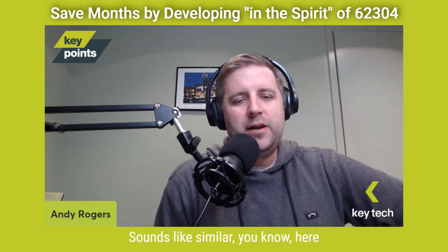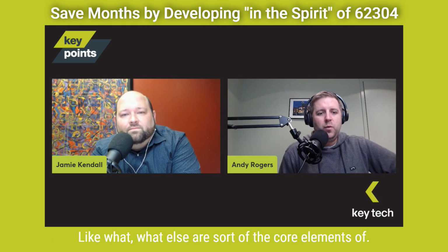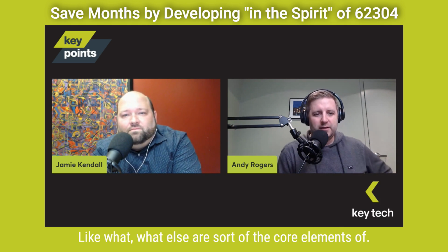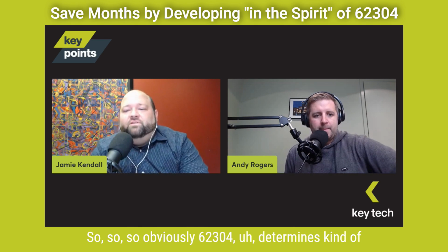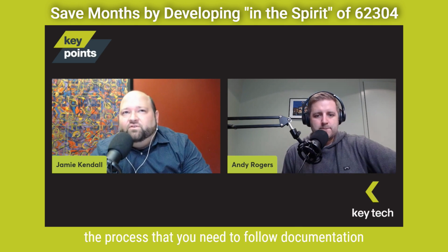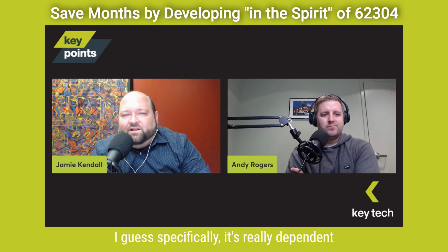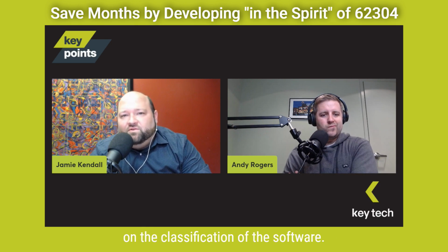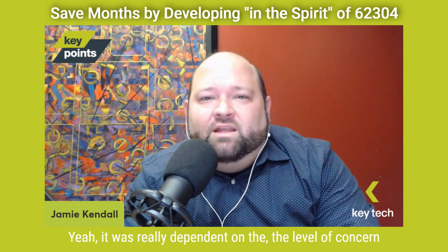Sounds similar here. You mentioned requirements and architecture a few times now. What else are the core elements of meeting the spirit? Sure. So obviously 62304 determines the process that you need to follow, documentation, implementation standards, things like that. Specifically, it's really dependent on the classification of the software. As I mentioned before, class A is something that isn't necessarily safety critical, and class C being the highest level of safety criticality. It's really dependent on the level of concern of your software and the software classification per 62304.